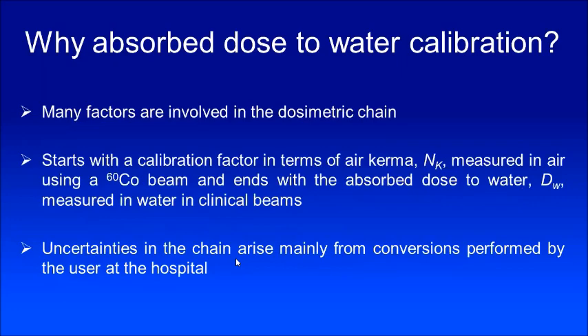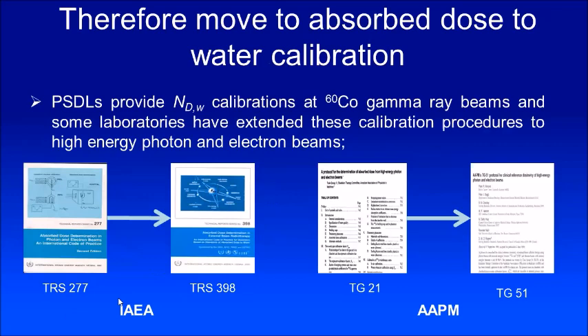Uncertainties in the chain arise mainly from conversions performed by the user at the hospital. To avoid that, in year 2000, IAEA came up with TRS-398, which recommended absorbed dose calibration in water and absorbed dose measurement in water directly. So TRS-277 became TRS-398. Subsequently, TG-21 of AAPM was also converted to TG-51, very similarly to what IAEA had done.